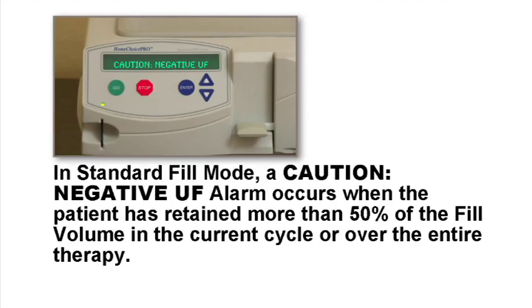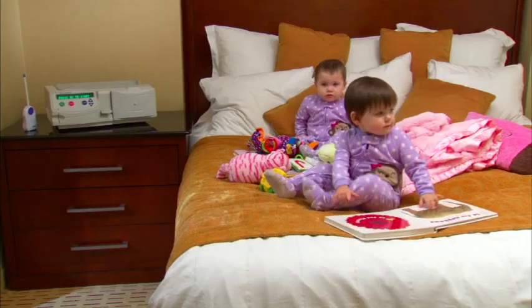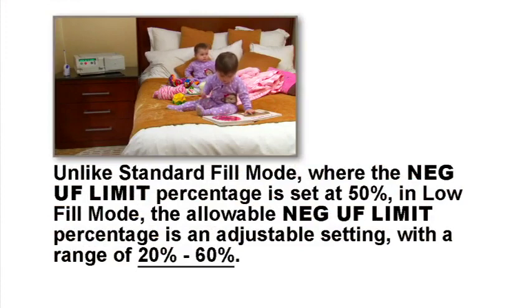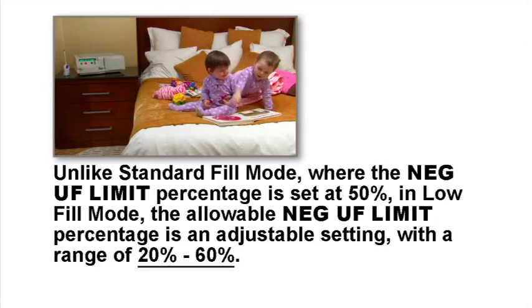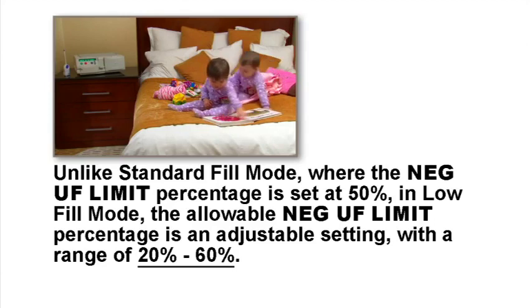In standard fill mode, a caution negative UF alarm occurs when the patient has retained more than 50% of the fill volume in the current cycle or over the entire therapy. Unlike standard fill mode, where the negative UF percentage is set at 50%, in low fill mode, the allowable negative UF percentage is an adjustable setting with a range of 20 to 60%.